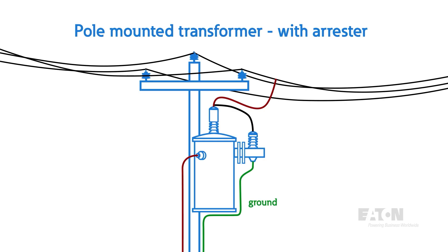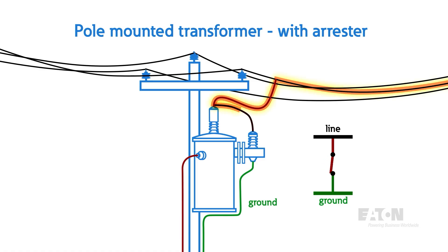For a transformer, the line lead will connect at the bushing and the load side is then connected to ground. Because of the semi-conductive behavior of the MOV blocks, the arrestor acts as an open switch for that path to ground. Utility engineers will select arrestors with a voltage threshold far above the system voltage to ensure that under normal circumstances, the arrestor never closes in to create unnecessary ground faults. However, when lightning strikes occur, the traveling overvoltage wave will cause the arrestor to conduct and provide a bypass path away from the equipment directly to ground.